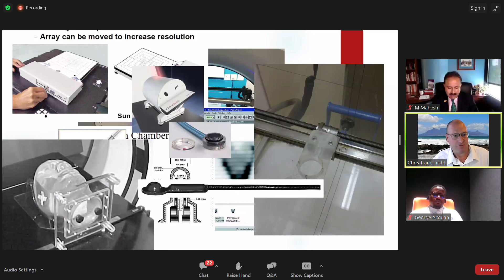You will need immobilization devices. Once again, if you buy a LINAC, the vendors will be happy to supply these. If you afterwards don't have it and you have to get this from the hospital budget, you will raise a lot of eyebrows because these things are expensive. When you specify, ask for 2 sets, because you want one on the CT scanner and one on the LINAC. You don't want your RTTs to have to walk around the division with these things tucked under their arms. They will thank you.